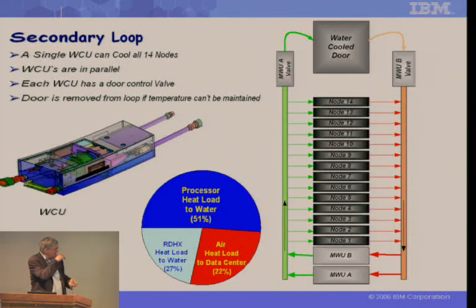This is the secondary loop. So this is a schematic of what I described before. Here are the modular water units, or water cooling units, at the bottom. They are redundant. So the water's distributed through all these nodes. And then what is remaining is taken out by a rear door heat exchanger that I showed you in that first slide on the back.